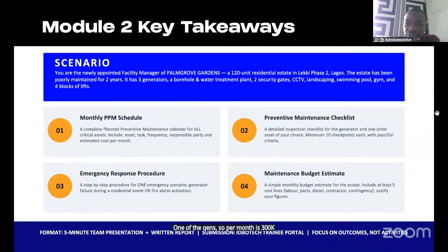Preventive maintenance checklist for the generator: check battery level every day, check the pressure, check temperature. Every day you record those three parameters. That's good, what else can we do?